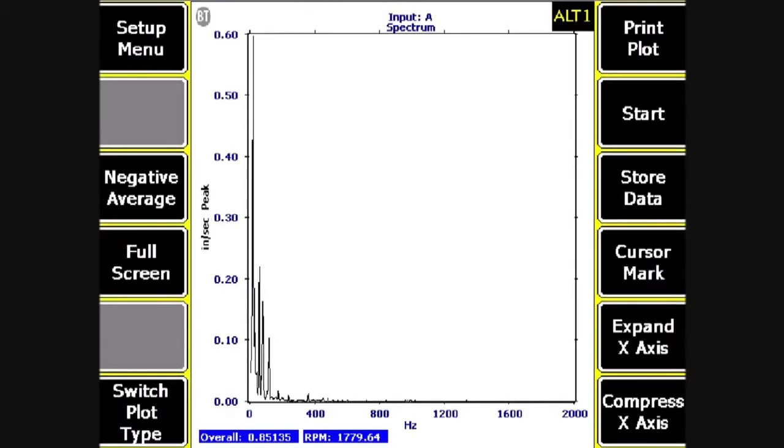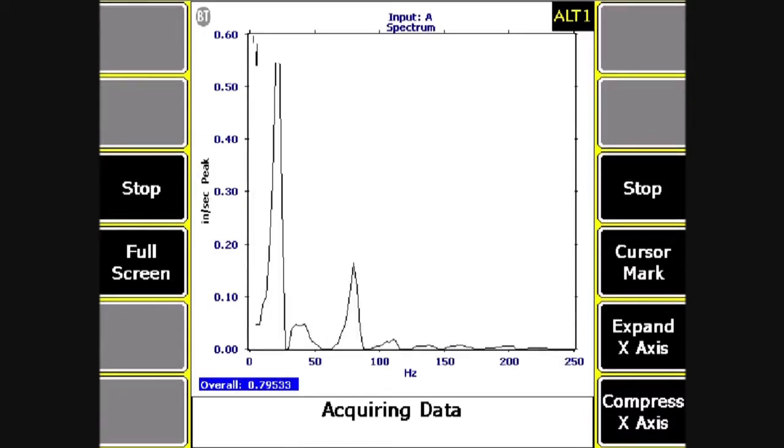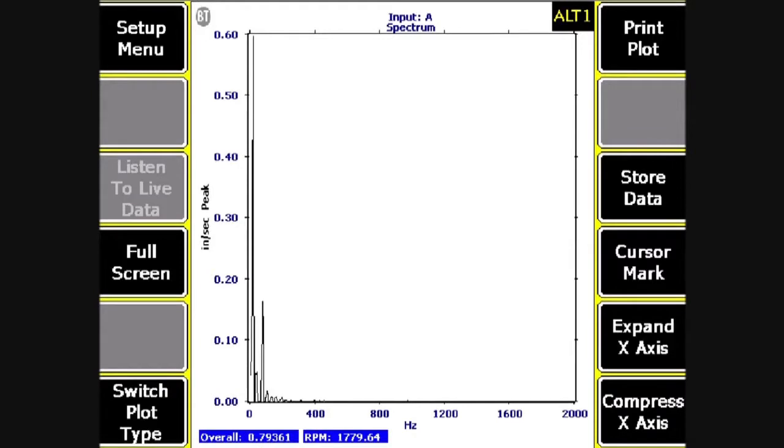Now F3 says negative average. So now what it's doing is recording the vibration just with the running of the machine, and it leaves me with the energy from the impact that I did. So I can press stop, F3, and expand the X axis.